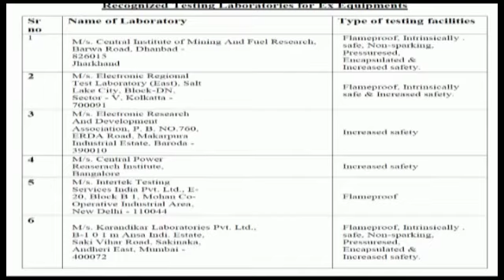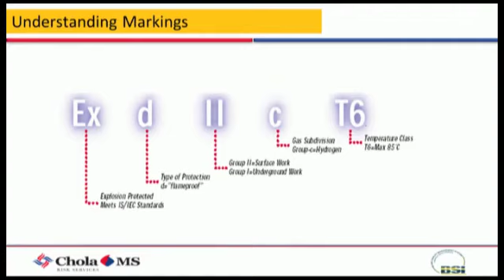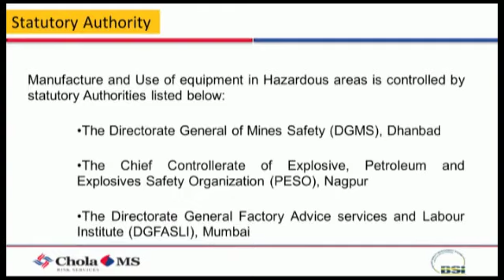So what we saw now is what you see on a nameplate like EXD 2C T6. T is the temperature, 2C is the gas group code, EXD is flame proof. All this put together will be available on the nameplate, based on which you can say whether you can use this for a hydrogen area or for propane or other material, depending upon gas and temperature all put together. You read this nameplate clearly. These are the manufacturing statutory authorities who control them.